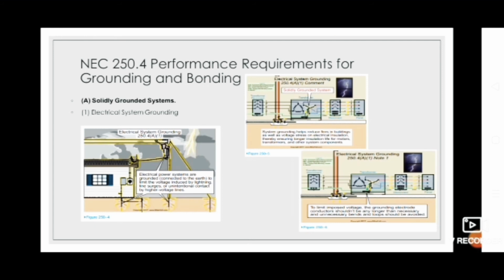System grounding reduces fire in the building as well as voltage stress on the electrical installation, ensuring longer installation life for motors, transformers and other system components. To limit imposed voltage, the grounding electrode conductor should not be any longer than necessary, and unnecessary bends and loops should be avoided.